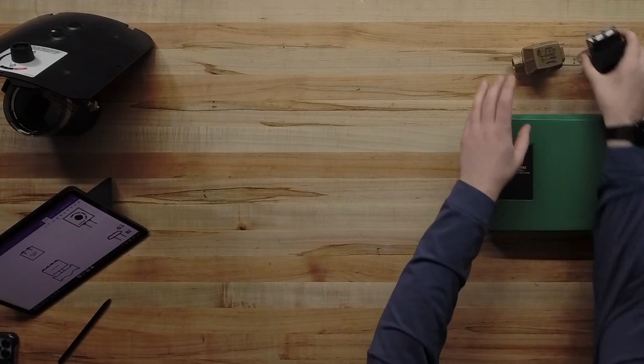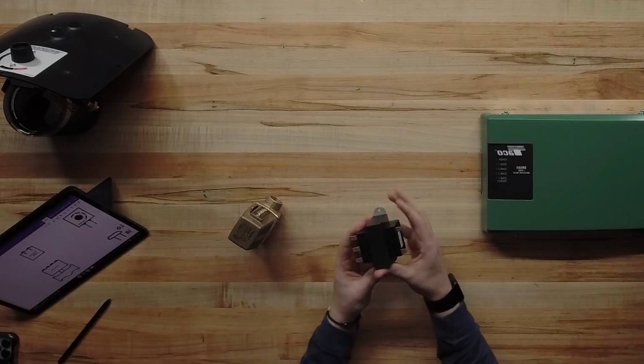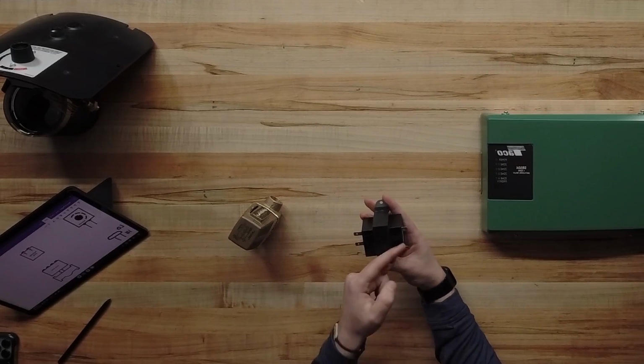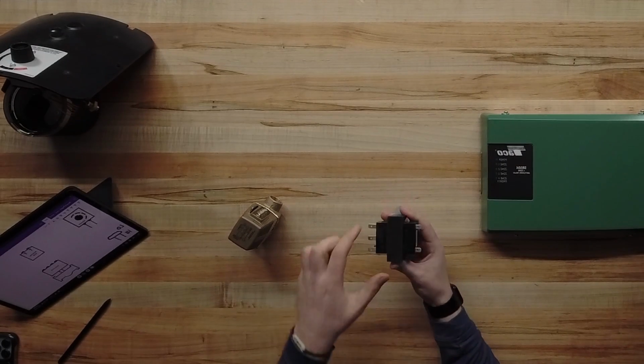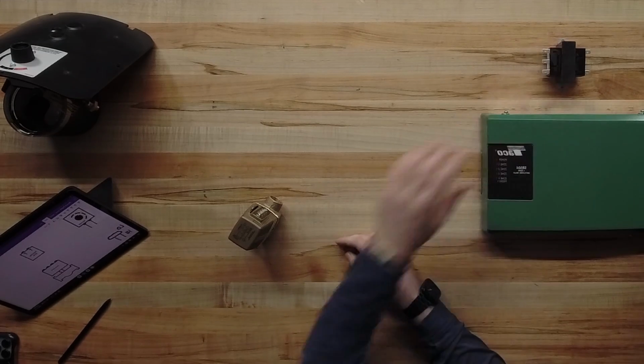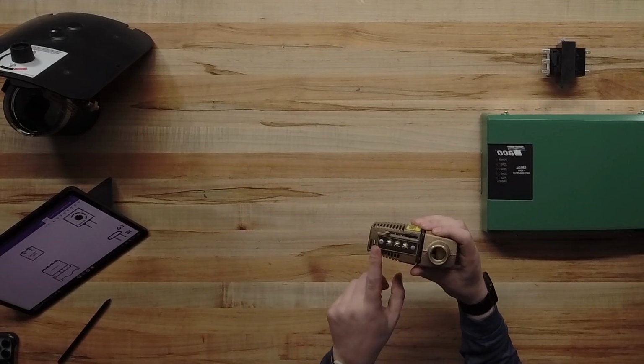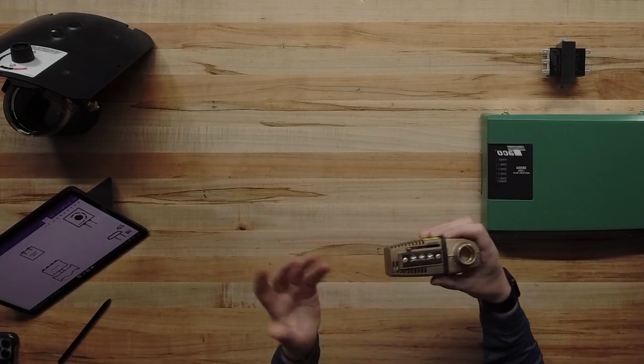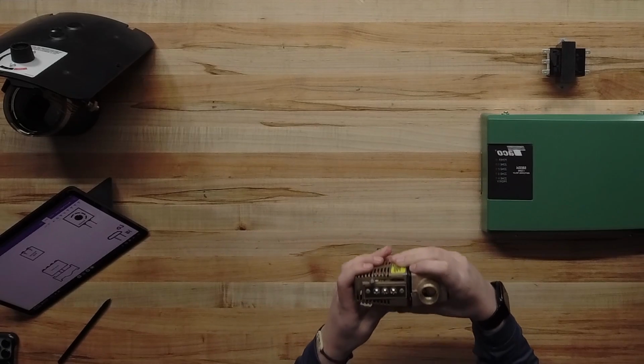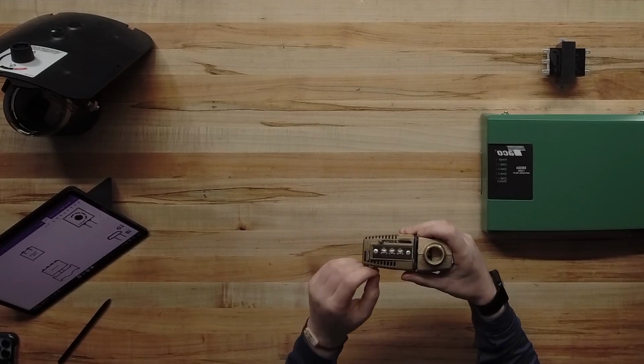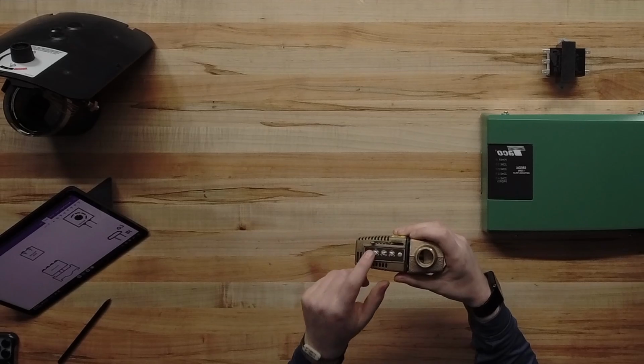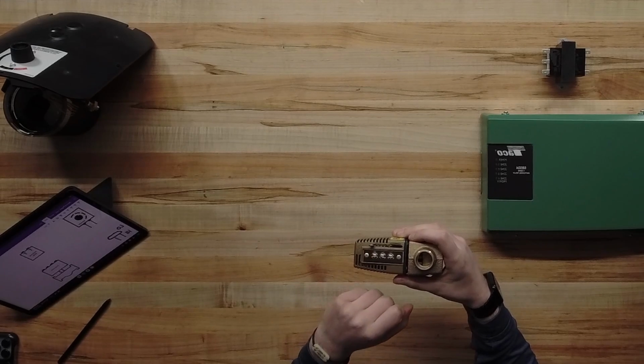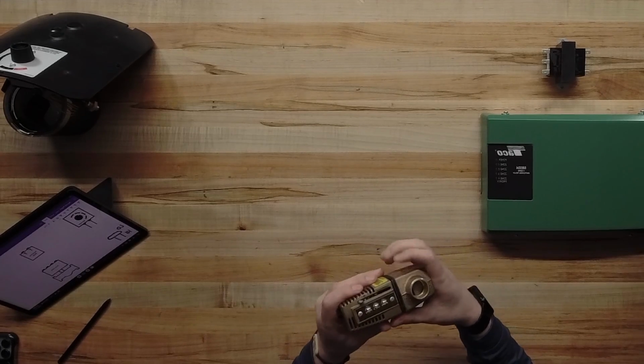The other example we had is a zone valve. So here I have a zone valve and a transformer. On the transformer, you're going to have your high voltage coming in one side, and low voltage coming out the other side from these terminals. And then on your zone head, this is that three terminal zone head. If you have a four terminal, just make sure you read those manufacturer's instructions. This is going to be very, very similar. But terminal one is what you'd want on this zone head to get that thing activated, opened up, and be good to go. So very straightforward.